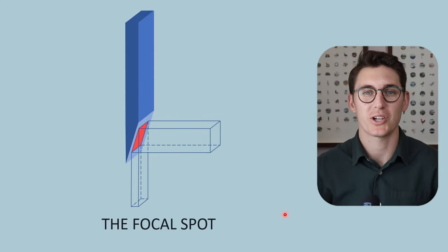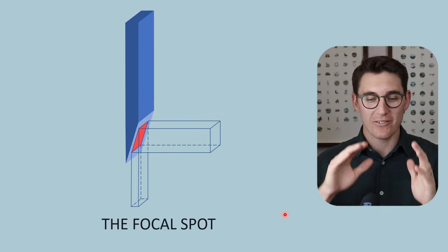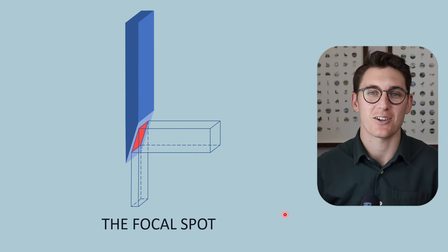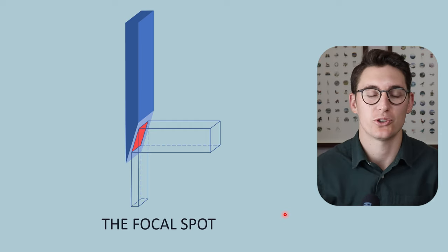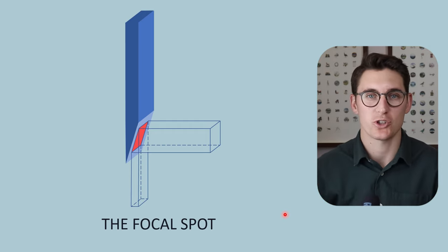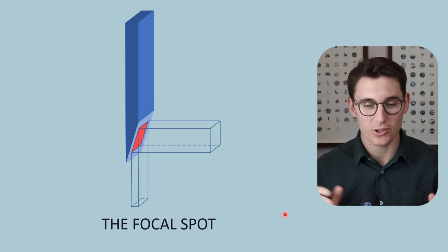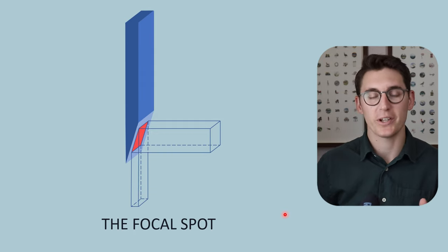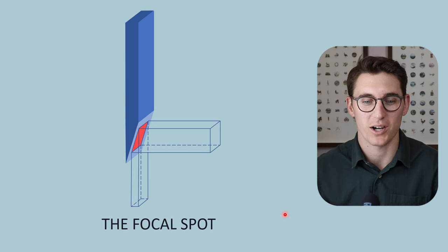As mentioned in the previous talk when looking at the anode, changing the anode angle will have a significant effect on both our effective focal spot as well as our field size, and consequently the resolution of our image. This all falls under the category of x-ray beam geometry, and I want to dive a little further into the geometry of the x-ray beam to show how we can change certain parameters to get the geometry we want for our patient.